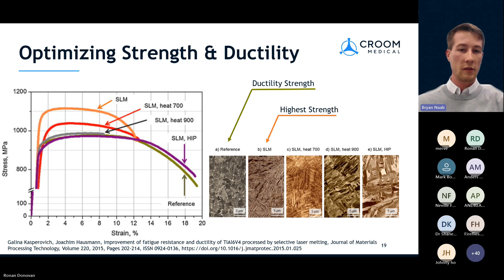So the data we get from the mechanical testing, the tensile test, is useful because it feeds into the design process of implants. It will give the design engineer some constraints with regards to the geometries that they can create with additive manufacturing for their implants. But it's a highly idealized test. So in a real world scenario, we often have fluctuating stresses, complex loading scenarios, and we generally don't see implants failing due to static tensile loads. So it's important to consider metal fatigue.